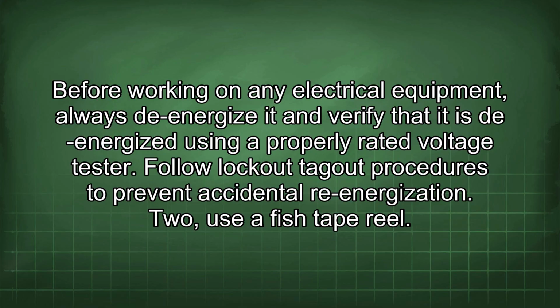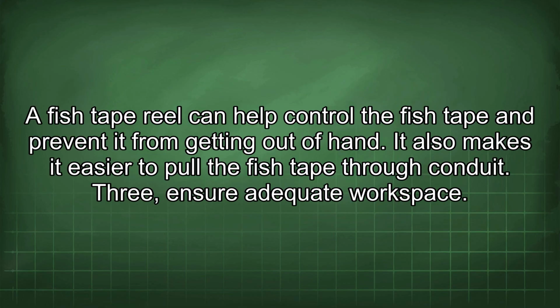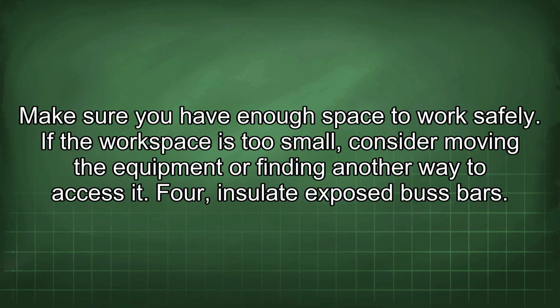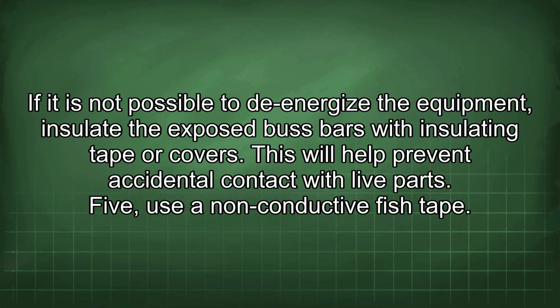2. Use a fish tape reel. A fish tape reel can help control the fish tape and prevent it from getting out of hand. It also makes it easier to pull the fish tape through conduit. 3. Ensure adequate workspace. Make sure you have enough space to work safely. If the workspace is too small, consider moving the equipment or finding another way to access it. 4. Insulate exposed bus bars. If it is not possible to de-energize the equipment, insulate the exposed bus bars with insulating tape or covers. This will help prevent accidental contact with live parts.